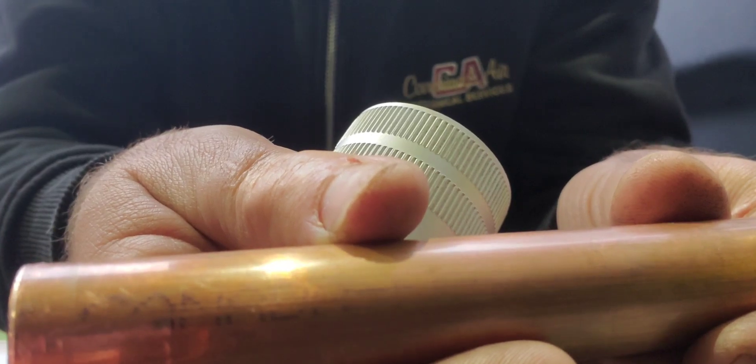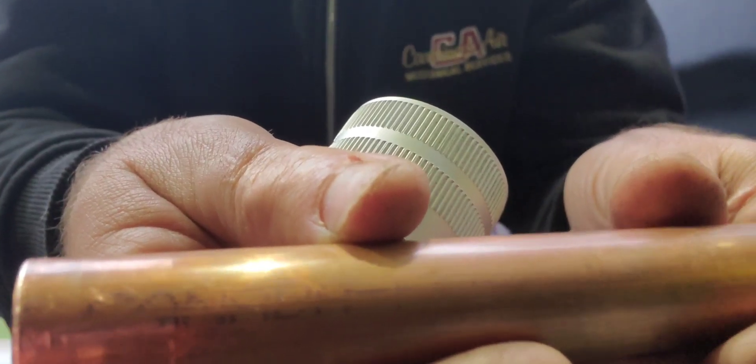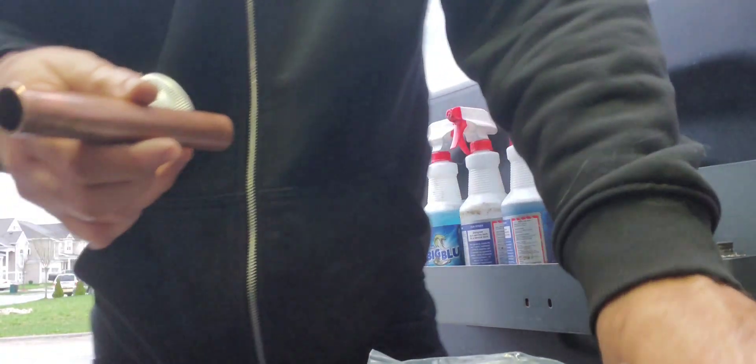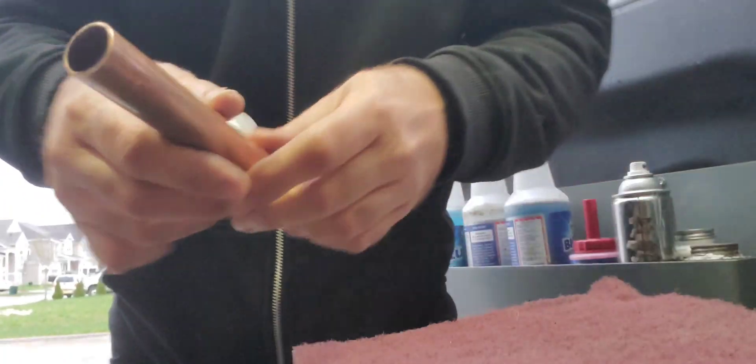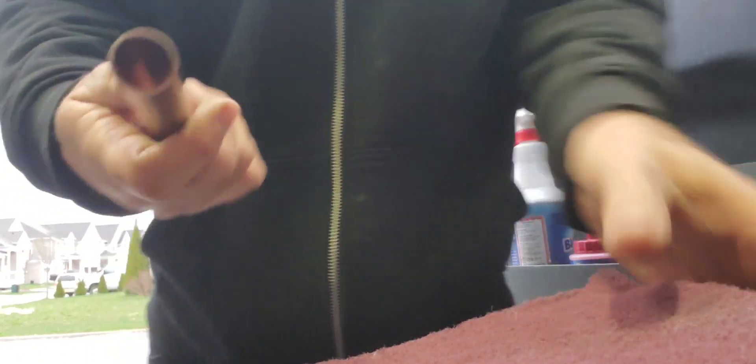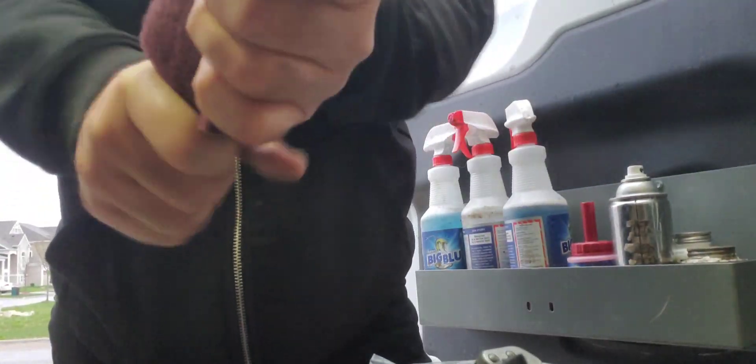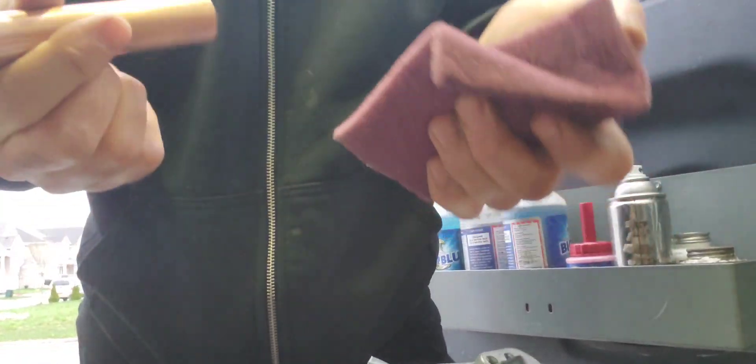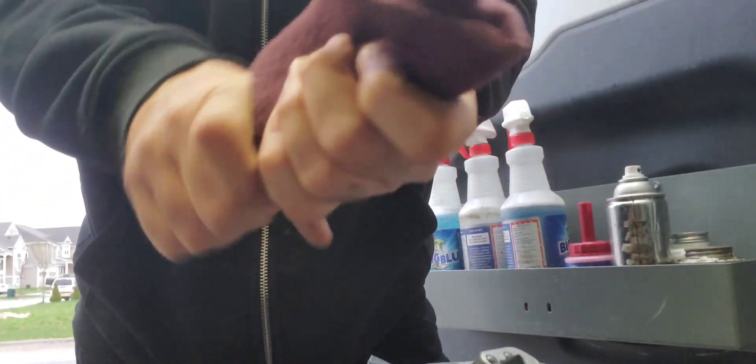There's some writing on that pipe, and it's super important to get rid of that. You're going to take the Scotch-Brite pad and clean that up really well. You've got to get all the deep scratches out. If you don't do that, you're going to have issues. People say that this is not a skill, but it's definitely a skill in the prepping that's involved.